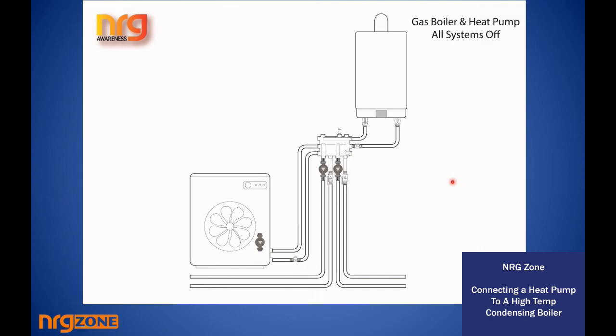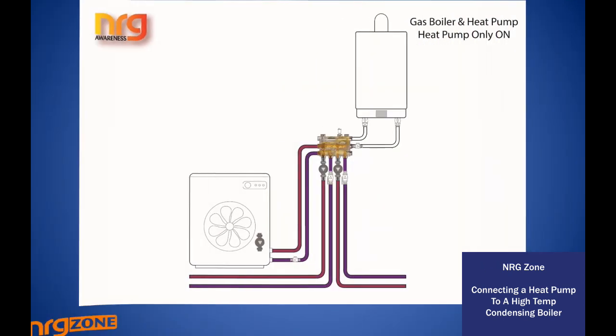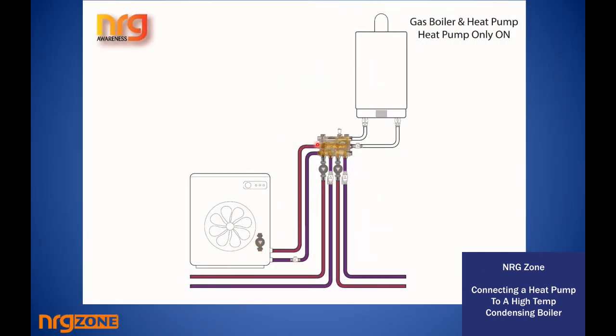Now we'll very quickly move through this job, and it's to show the function of how the different ports and chambers work. It's an example only. If I have a heat pump and a gas boiler, I can take the flow from my heat pump into the middle chamber, and the middle chamber passes this opening here, which will allow heat to be drawn up if the zones are pulling water. So if zone 1 is taking heat, or zone A is taking heat, and zone B is taking heat, and the heat pump turns on, then the heat will be delivered in from the heat pump across the chamber.